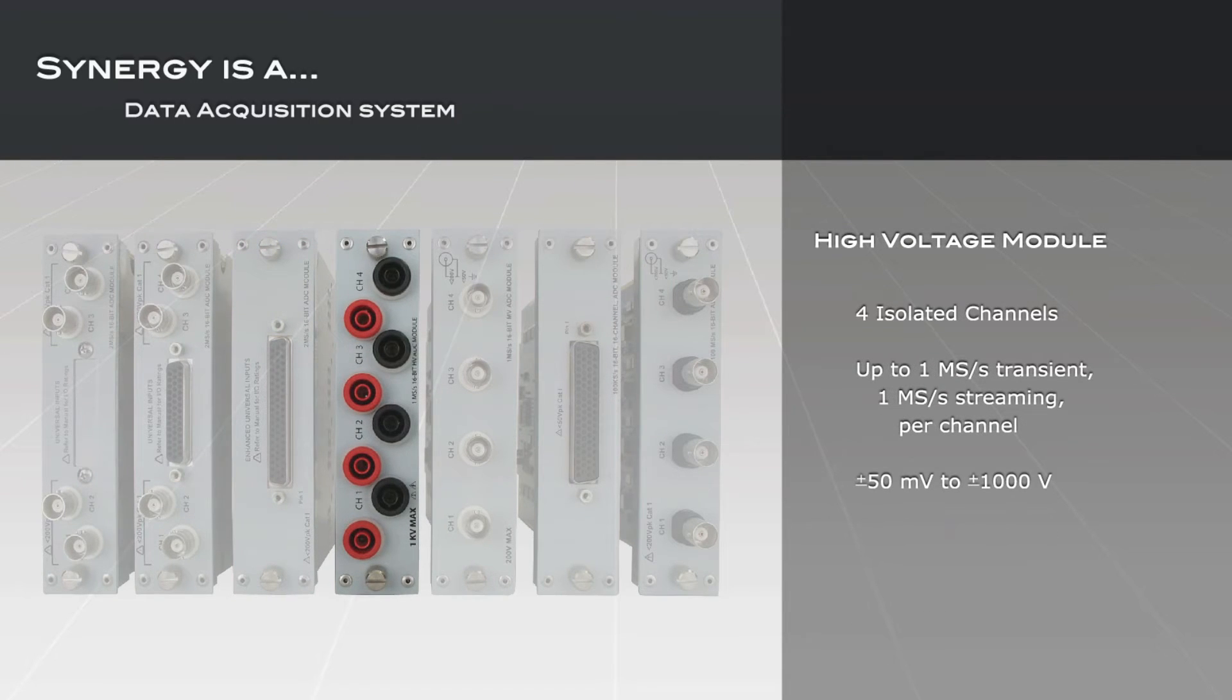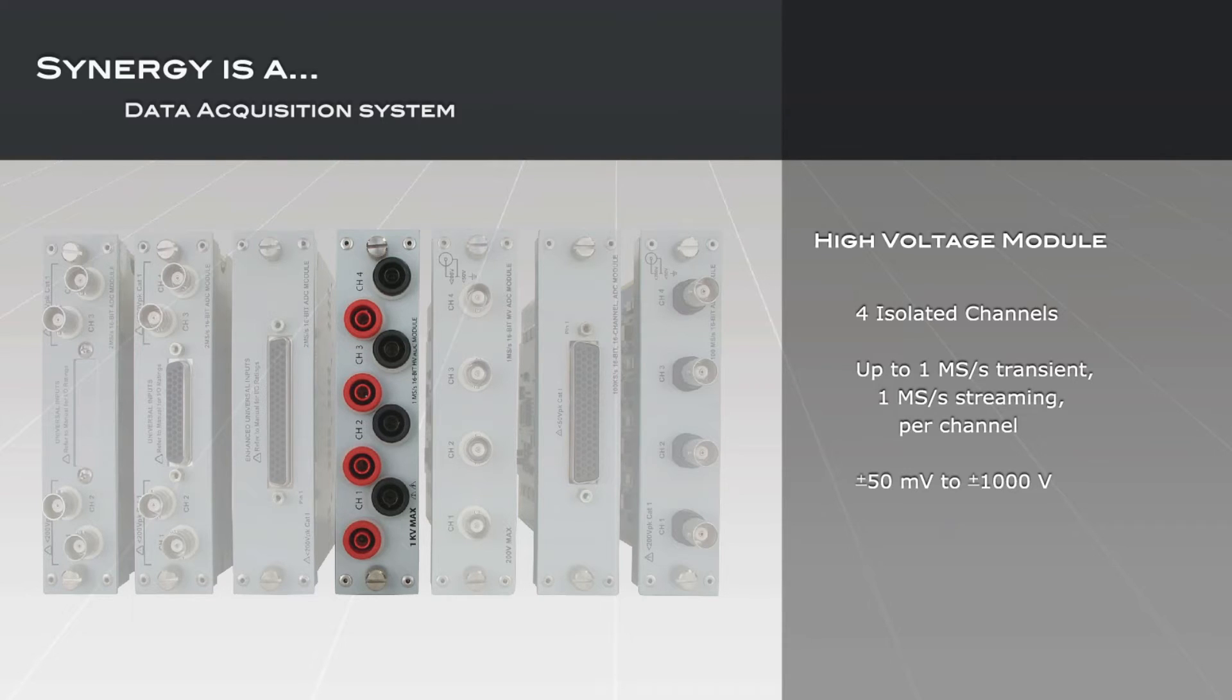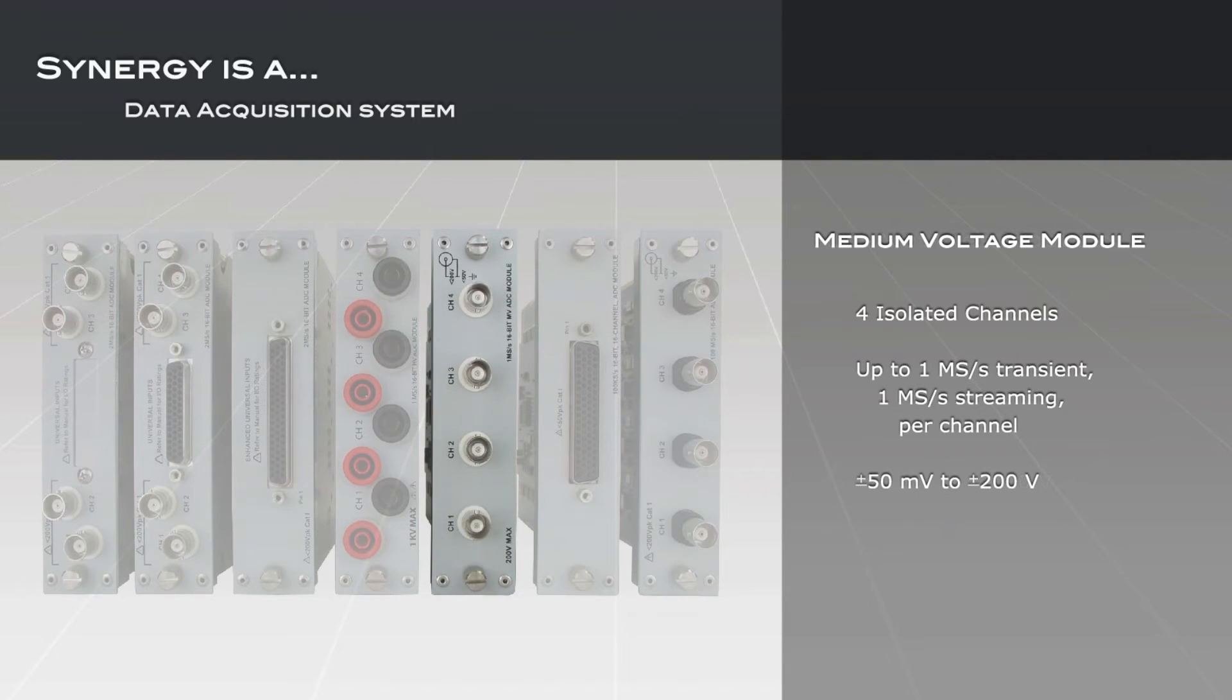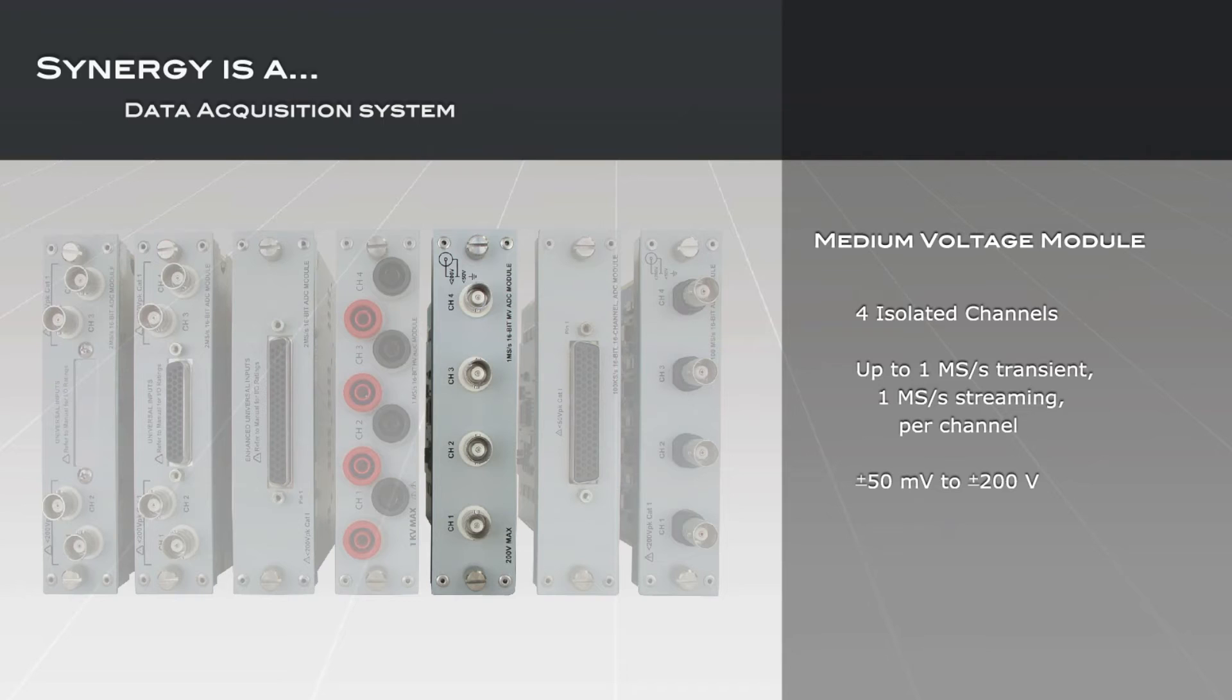The high-voltage input module offers an input range up to plus or minus 1,000 volts and a 2,000 volt peak channel-to-channel isolation for high-voltage and high-power applications. The medium-voltage input module provides a cost-effective 4-channel solution for general-purpose voltage applications offering plus or minus 50 millivolts to 200 volts and floating differential inputs.